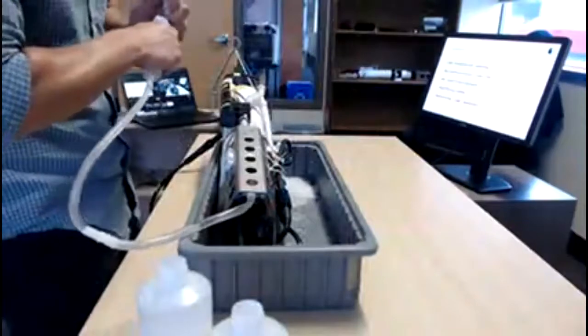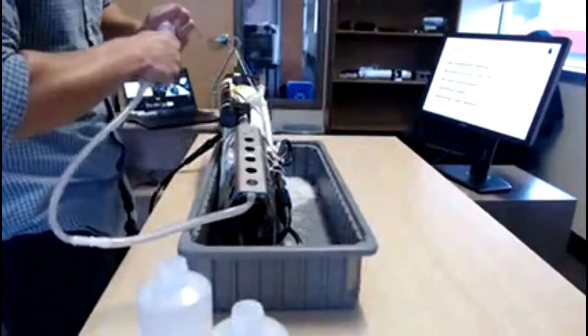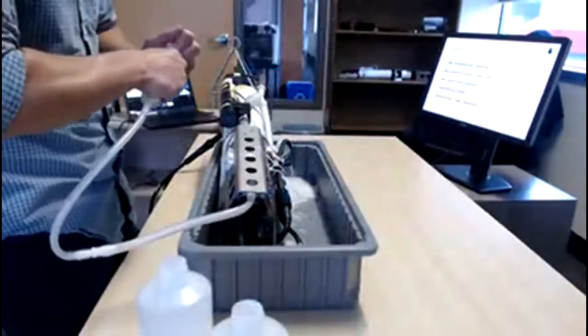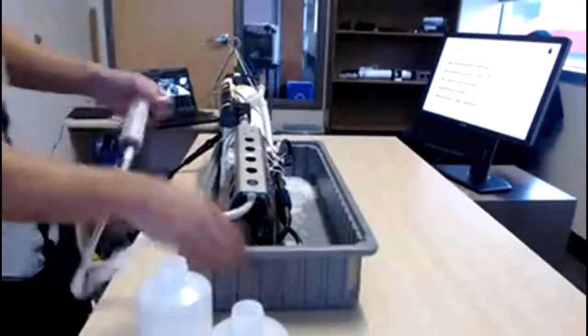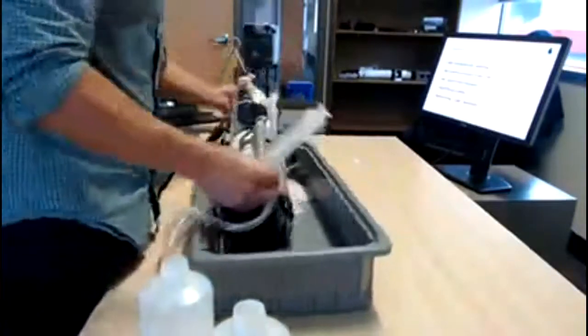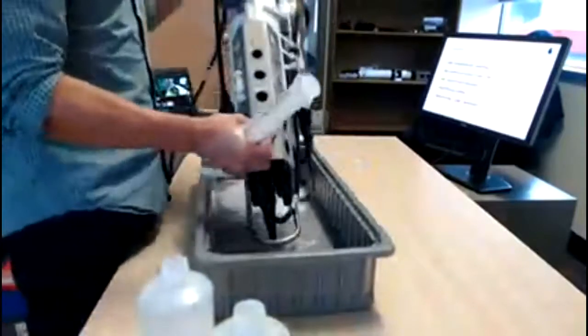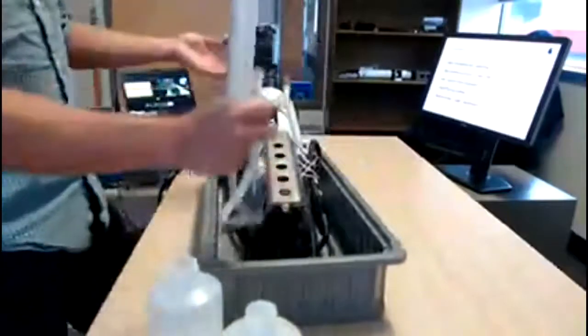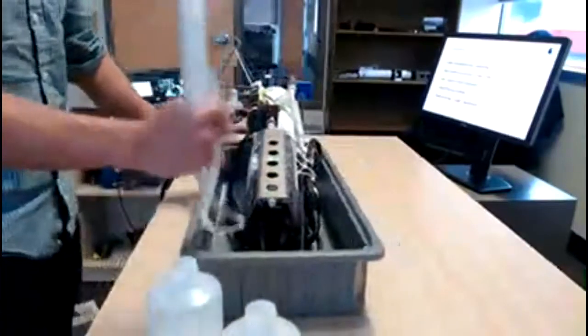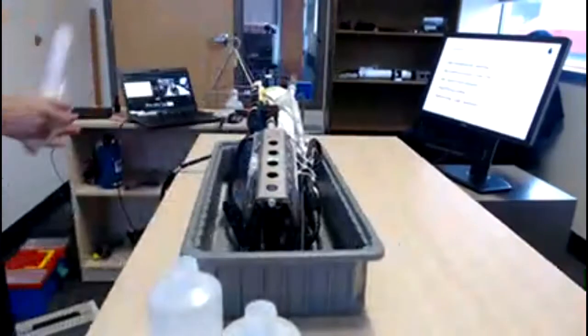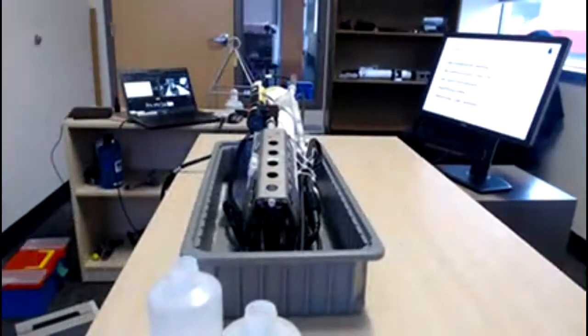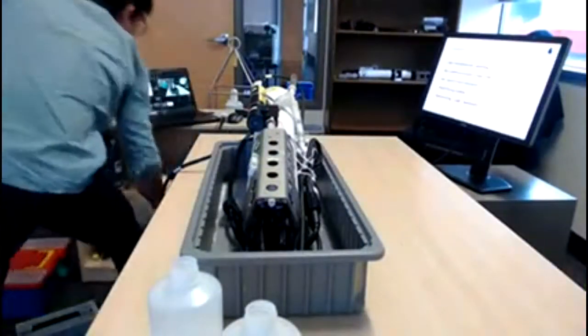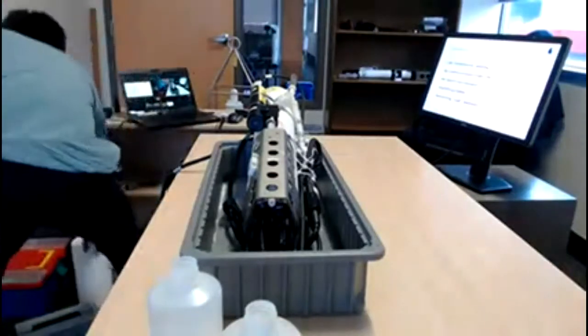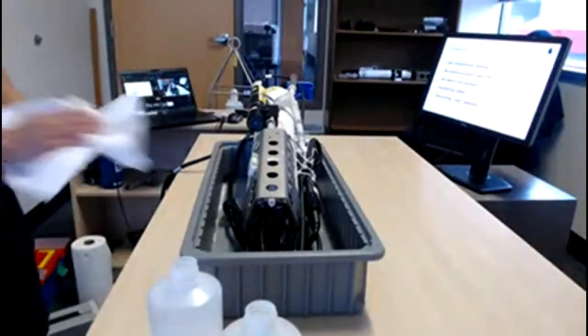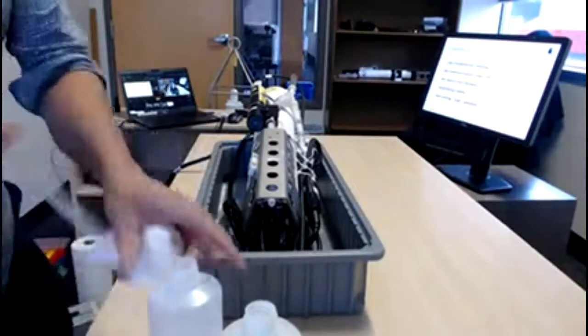You're just flushing a lot of soap through the system and just trying to get it out as much as possible. So make sure you're catching this in a basin, and try to empty as much of the Triton X out of the CTD's plumbing as possible. What you'll often find is after you go through that cleaning procedure, your conductivity signal will probably increase a little bit back to what it was when it was first calibrated by Seabird.